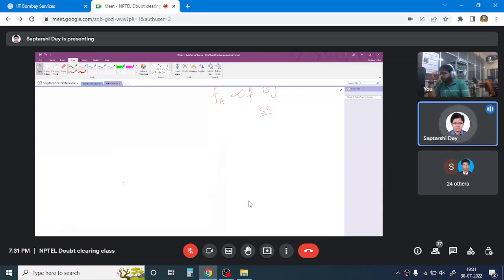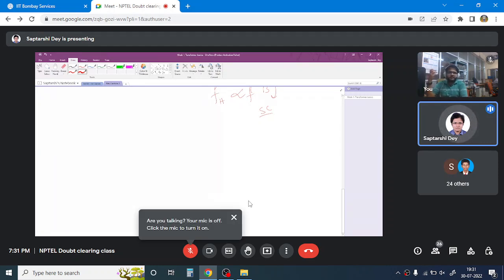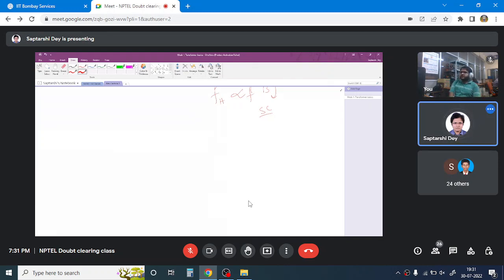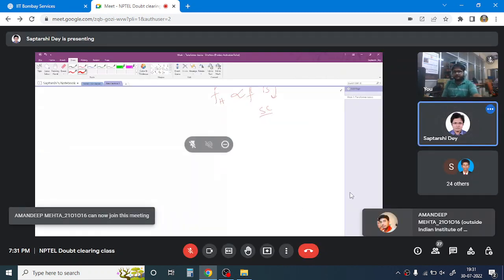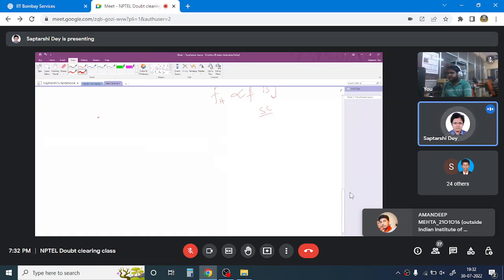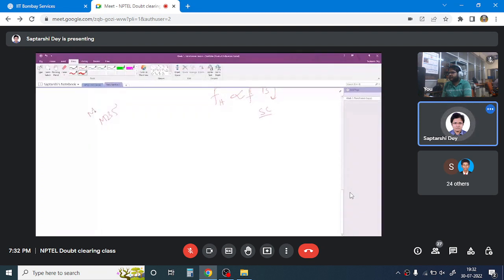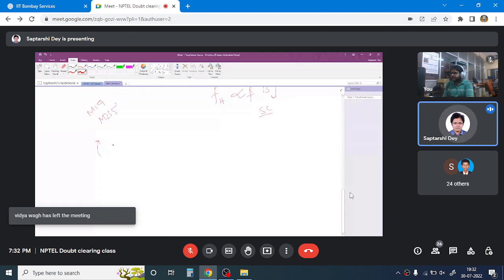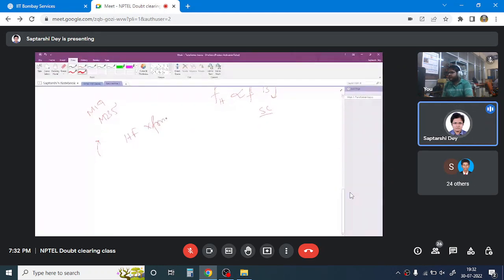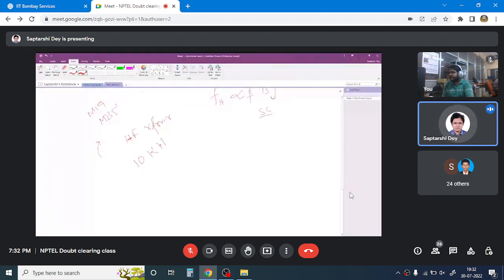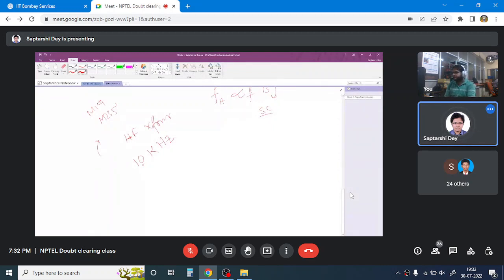Since you talked about core loss and frequency, let me tell you one more thing that might not be very relevant here. The high frequency transformer that someone was talking about, the materials used there are not the same as power transformer materials. The power transformers or distribution transformers that you see are very low frequency, 50 hertz transformers. So the material used there is a kind of electrical steel, like M235 can be one option, M19, these kinds of steels are used. But if you go to a high frequency transformer, say 10 kilohertz, in the power electronics area 10 kilohertz is a very low frequency. High frequency people are nowadays working in hundreds of kilohertz or maybe even more.